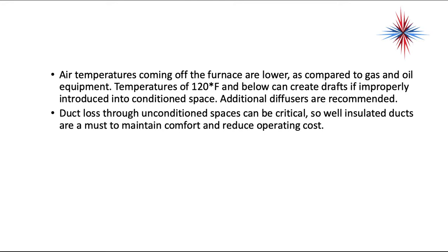Temperatures of 120 degrees and below can create drafts if improperly introduced into the conditioned space. Additional diffusers are recommended. Duct loss through unconditioned spaces is critical, so well-insulated ducts are a must to maintain comfort and reduce operating costs. The lower the temperature of the air coming out of the registers, the more your customers are going to complain of drafty environments.